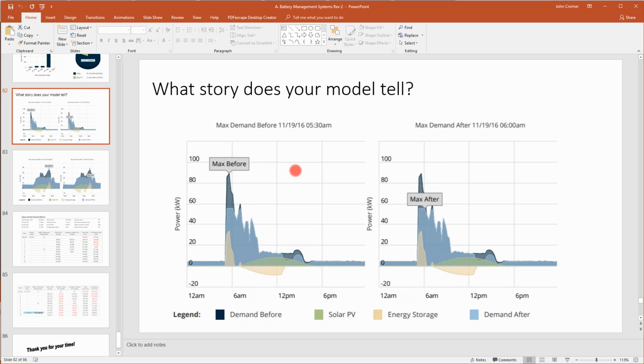Furthermore, batteries are coming to the market and saying, well, let's take that industrial facility that might need a 10 megawatt solar array to offset its electric bill fully. But really, it's on a peak rate structure where instead of being billed for the volume under this curve, like the kilowatt hour, which is how residential electricity is billed, high demand customers are billed for this maximum demand.